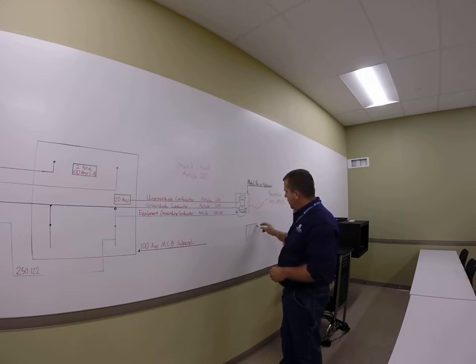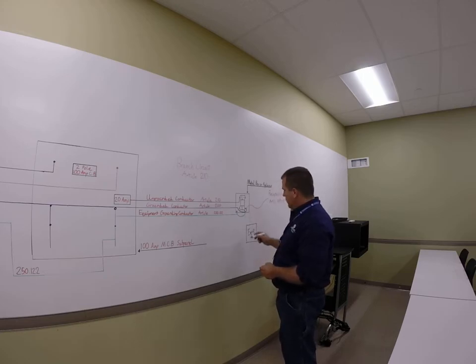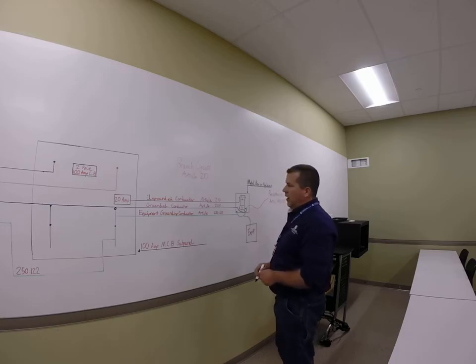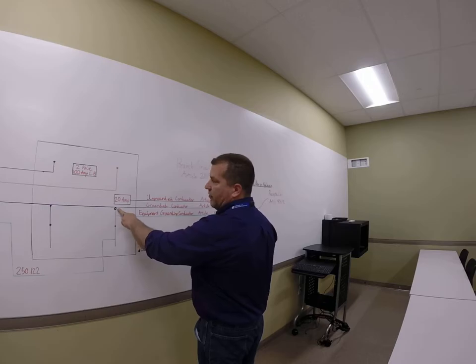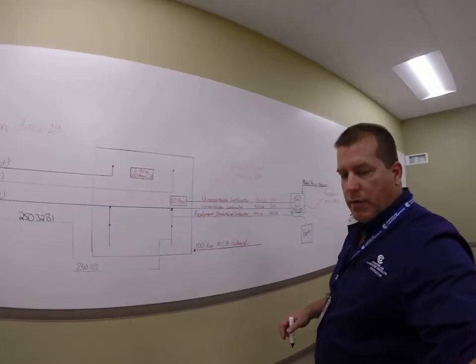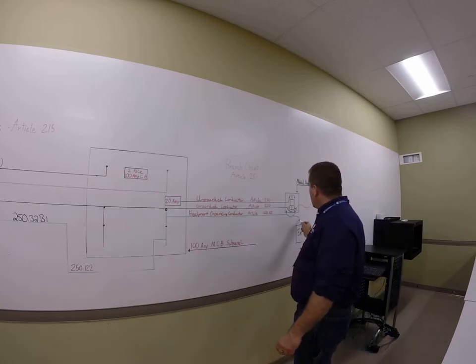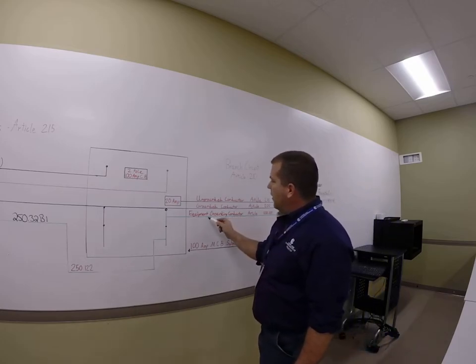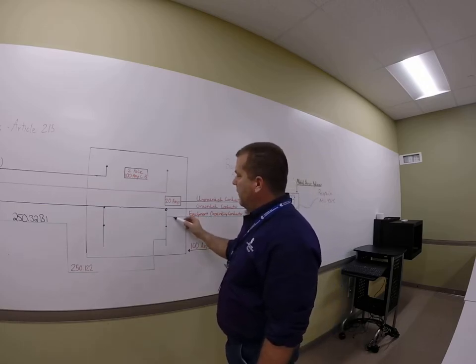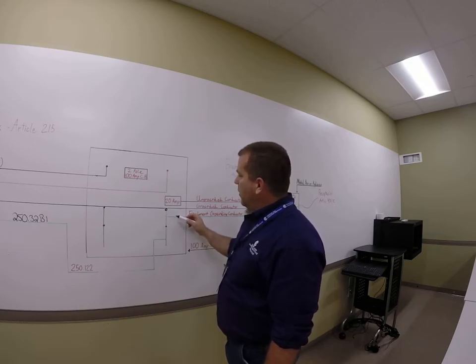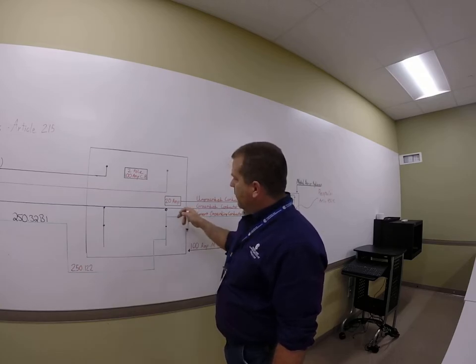and let's say something happens to this piece of equipment. Something happens, and I get a ground fault. Hot hits the ground. If my hot wire hits the ground wire, and I'm also bonded to my neutral bar over here, what's going to happen when hot hits ground is all that excessive current is going to travel on this equipment grounding conductor, and what it wants to do is facilitate the overcurrent device to open.